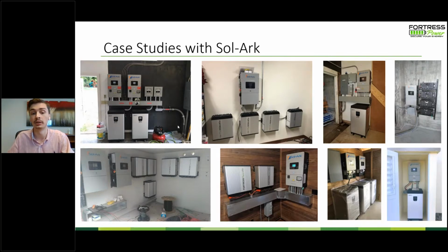So it's really important, if they are saying 10,000 cycles, to ask: does this take into account charging and discharging rates, temperature? Does this take into account all these other factors? Because it definitely doesn't. Now, Fortress, we do 6,000 cycles. It's a more conservative number, but it's more realistic with how we expect people to use the battery, in congruence with our warranty. So that's basically the gist on the at least 10,000 versus 6,000 cycles of Fortress versus SimpliPhi.